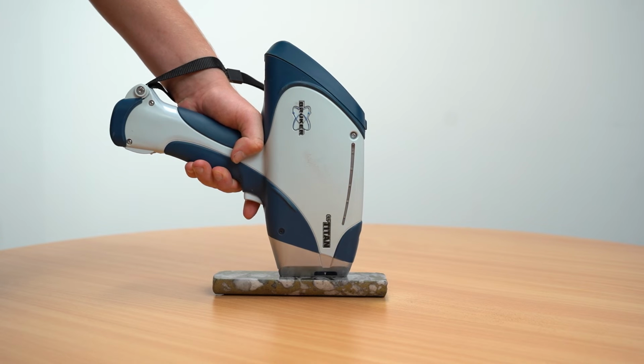This would mean that the calibration you are using will not be able to calculate the quantity of elements correctly, as you do not have all the information that it needs. It is therefore important to let the analysis run for the full time that has been set to ensure you are getting accurate results.